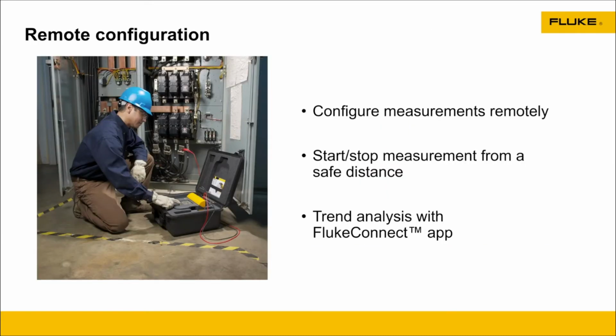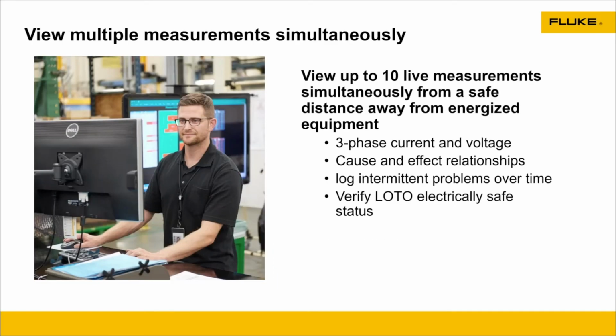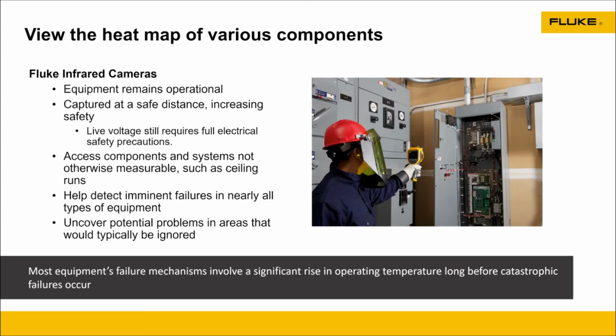Now, there are also remote configuration devices like an insulation tester, where we can set this up and do high voltage insulation tests from a distance, using our smart device to configure and start and stop a test, again using Fluke Connect. But the theme here is keeping you away from some type of potential energy, so you're safe. And on this, you can even save or look live at up to 10 measurements while you're doing it. So we've talked about staying away, whether we're making those voltage measurements or those current measurements, and potentially how to do that using Bluetooth devices.